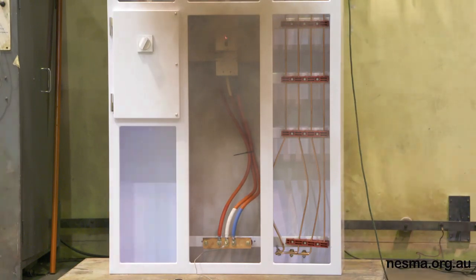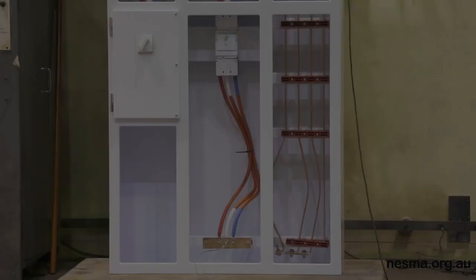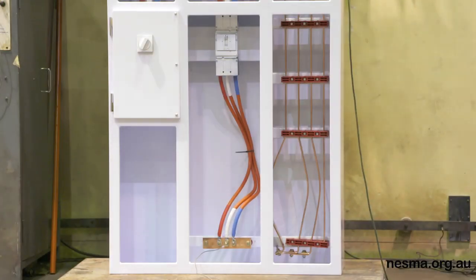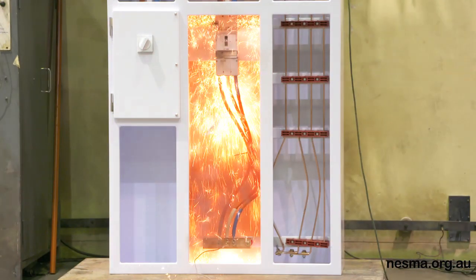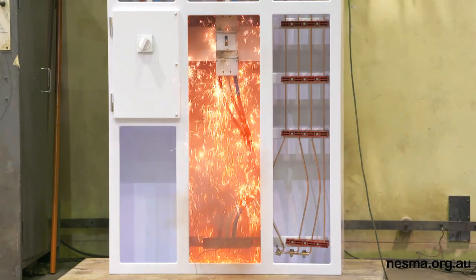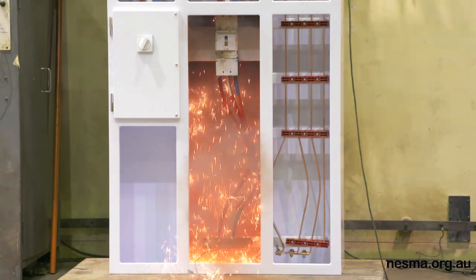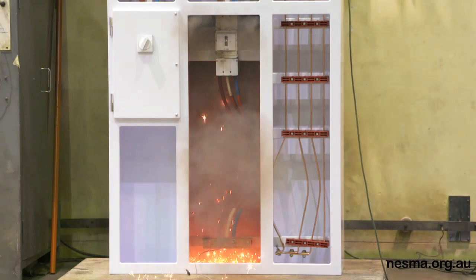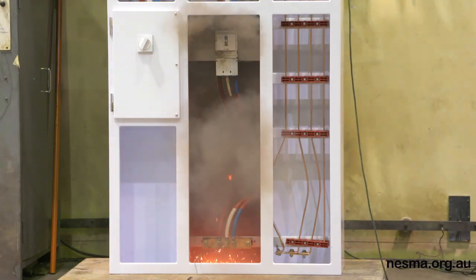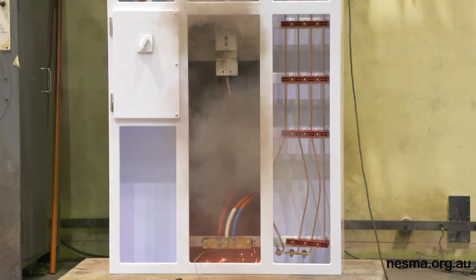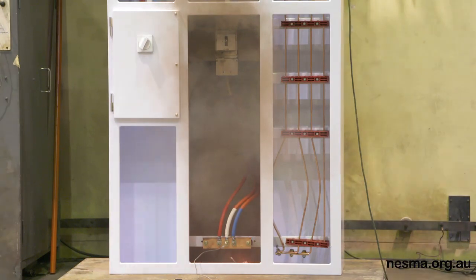So that operation, you've seen a little bit of afterburn because you've got lots of gases intumescing from the product that the circuit breaker is made from. What we are seeing is the circuit breaker operating successfully with that 50 kA fault level. So the amount of arc product and the pressurization that would occur should there have been a door on the front of that cubicle is typical and expected. So it's not like a small miniature breaker that's operating at a 3 kA fault level.